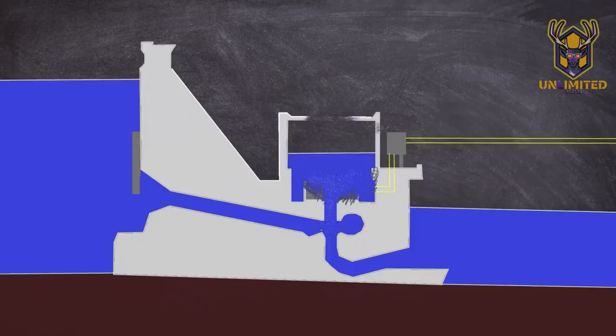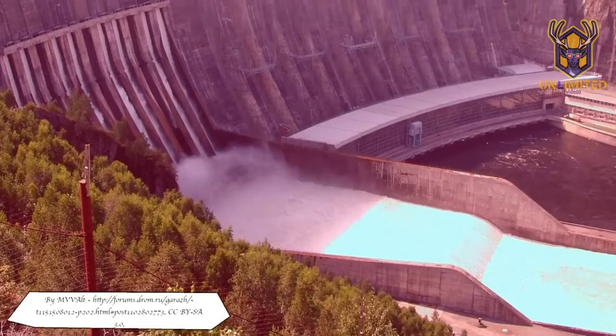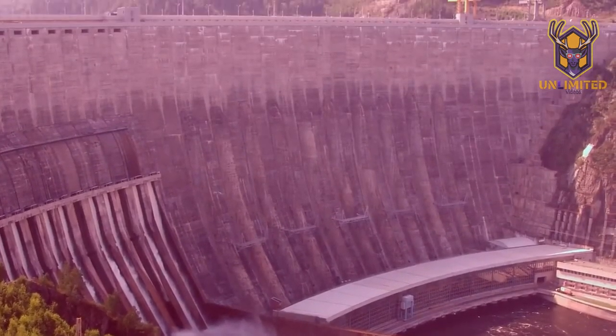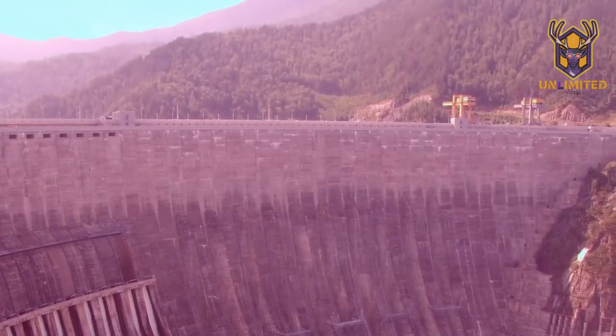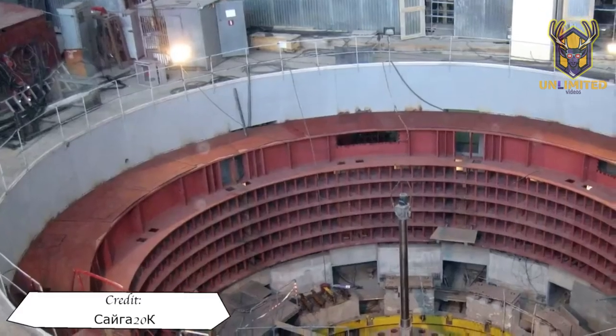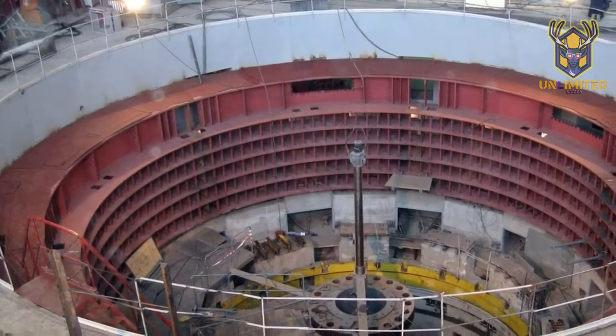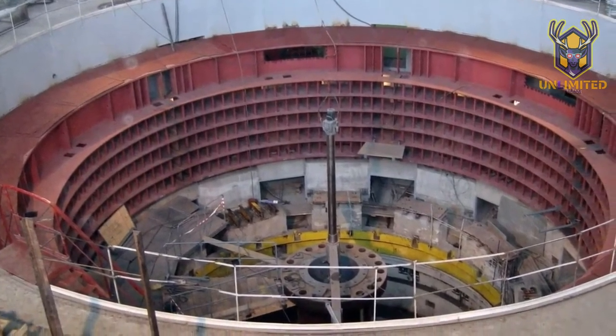The control room became aware of the disaster as Unit 2's electrical power output dropped to zero, causing a local blackout. The water soon cut through the structural steel and the turbine gallery roof collapsed. The steel gates to the water intake pipes, weighing around 150 tons each, were closed manually — held up by hydraulic jacks — a process that would take at least 25 minutes, all while water continued gushing from the destroyed Unit 2. The emergency diesel generator was started and the spillway gates of the dam were opened. Units 7 and 9 continued to operate after their safety shutdown systems failed to trip, becoming submerged and causing further damage. Units 2, 7, and 9 were completely destroyed, with the remaining units experiencing serious damage.